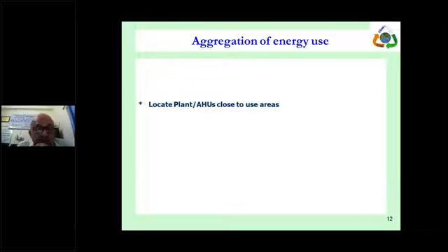Aggregation of energy use is another principle which we can apply in air conditioning. So this applies where many times plants are located a little far away, and all the way chilled water and things are run towards AHUs. So you are not only incurring more cost, but also more running cost and more maintenance problems. Many times it happens due to the paucity of space. Sometimes the designer won't allow it: no, I don't want this plant here, noise will come. So they locate the plant a little far.